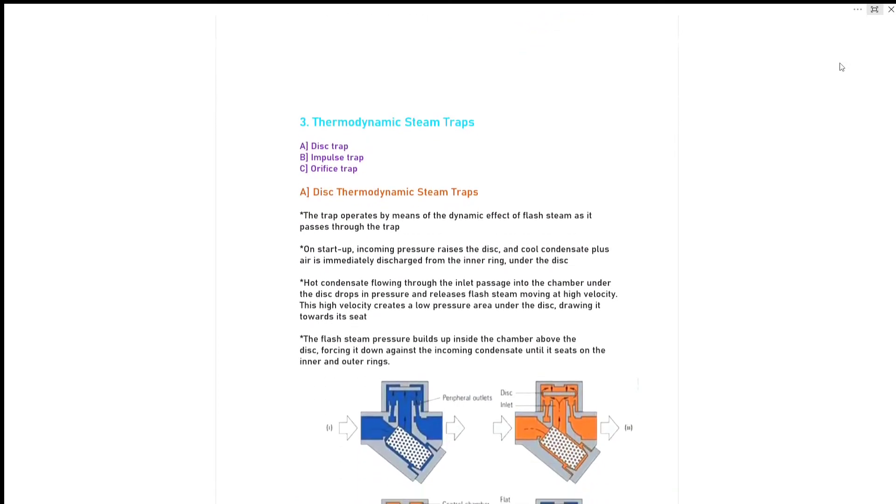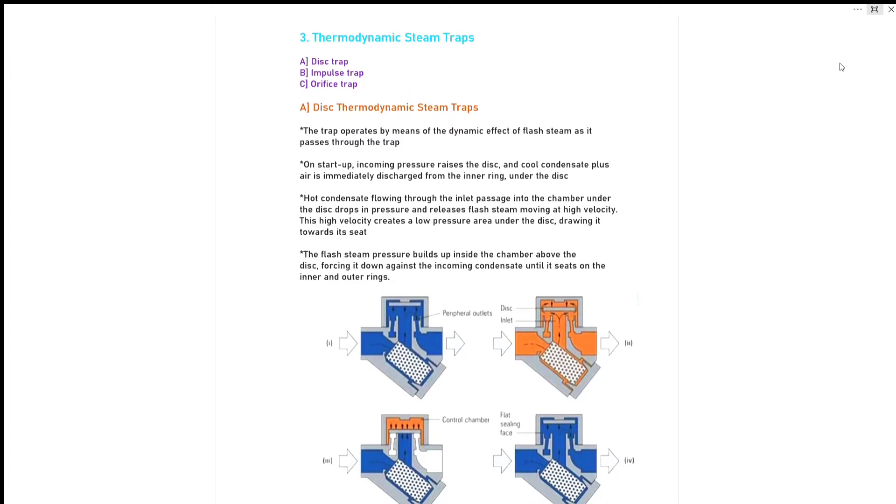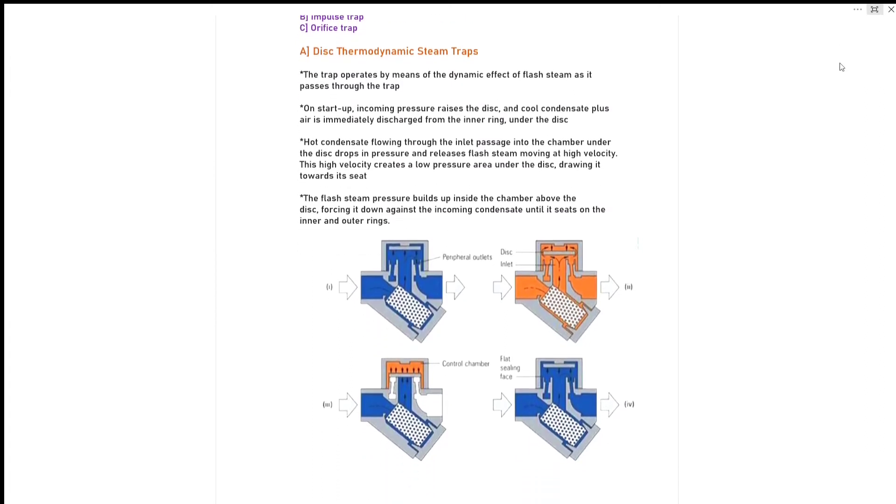Our last major type is thermodynamic steam trap. It has three types: disc trap, impulse trap and orifice trap. A trap operates by means of dynamic effect of flash steam as it passes through the trap. On startup, incoming pressure rises the disc and cool condensate plus air is immediately discharged from the inner ring under the disc.